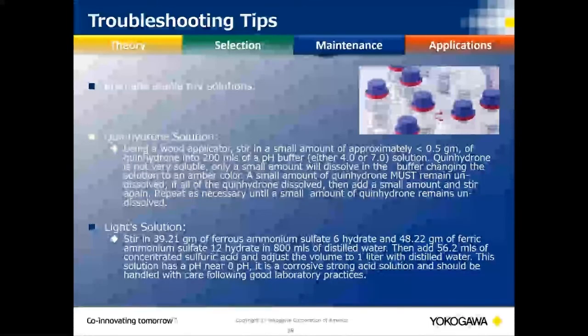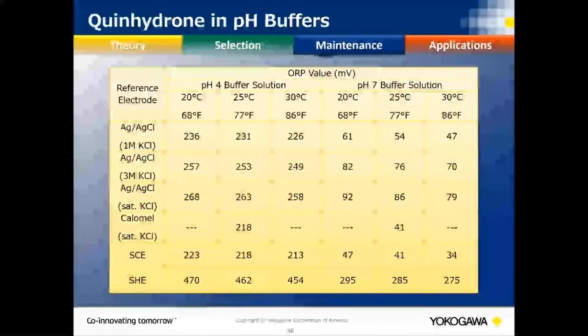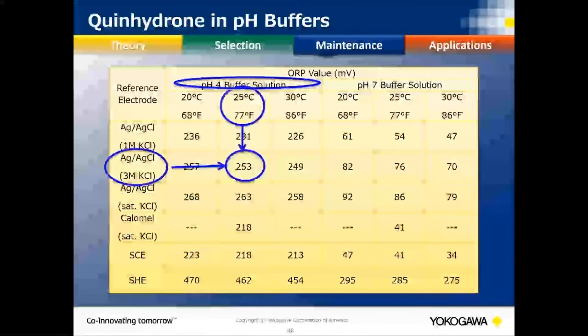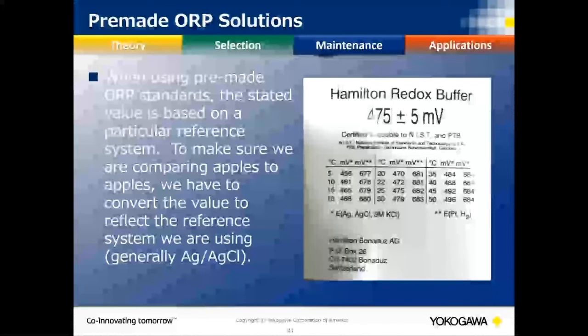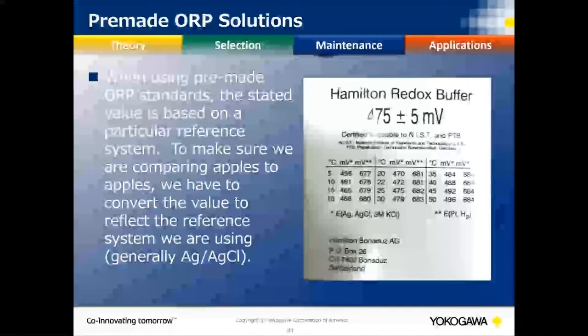With pre-made solutions, if it's within shelf life and properly maintained — meaning you took a sample, used it, and threw away the remainder without pouring it back in the bottle — you know it'll read 475 millivolts. It's a good reference point to resolve 'who's right, who's wrong' between your lab and online measurement.